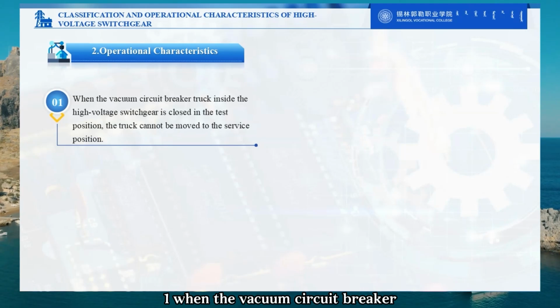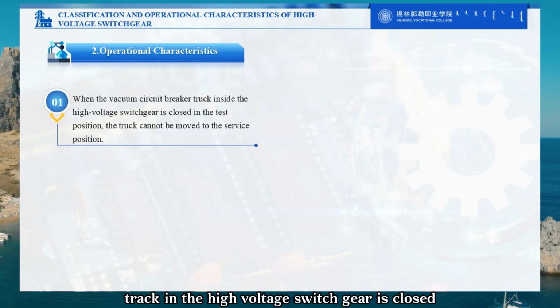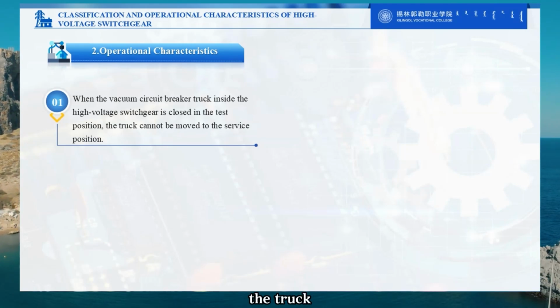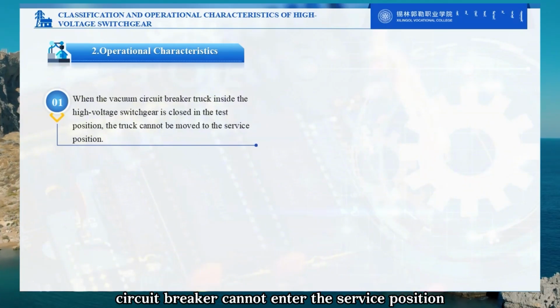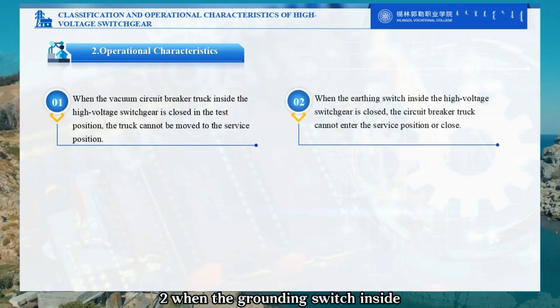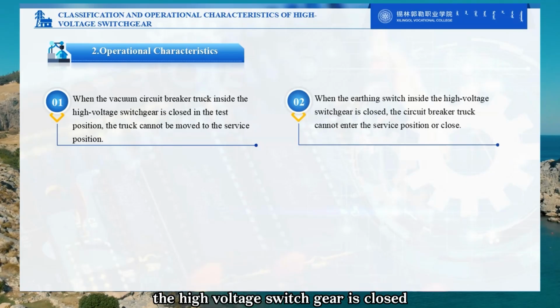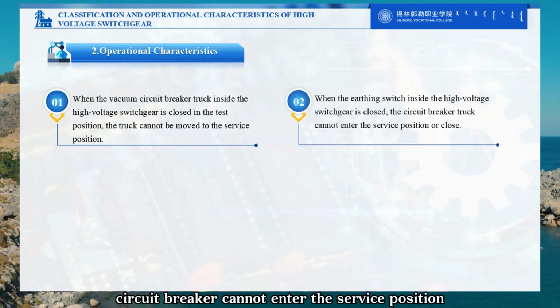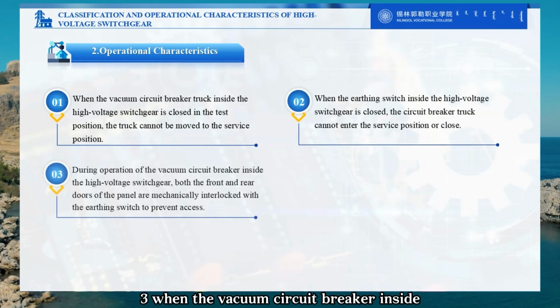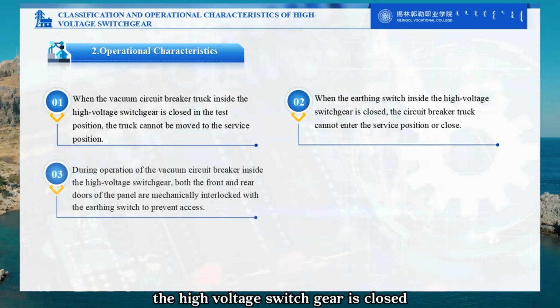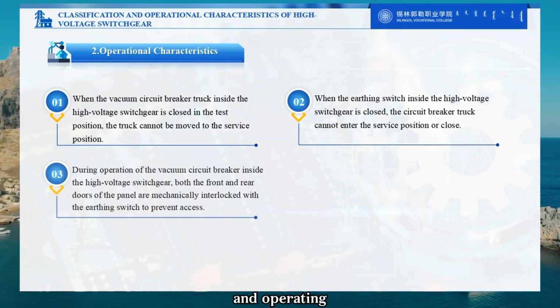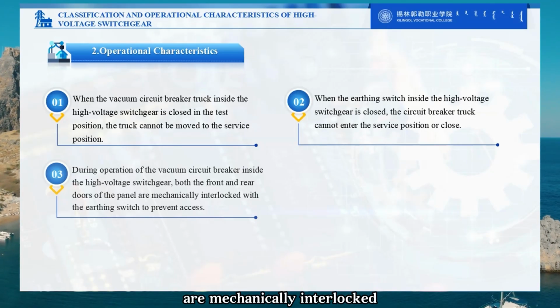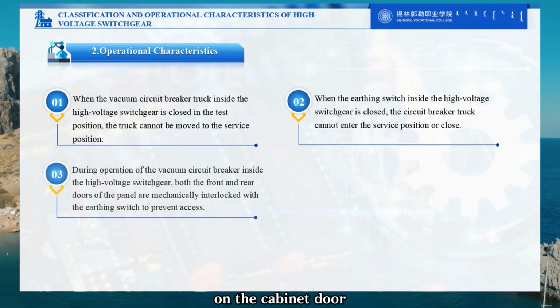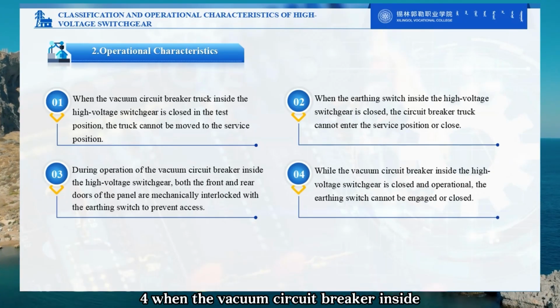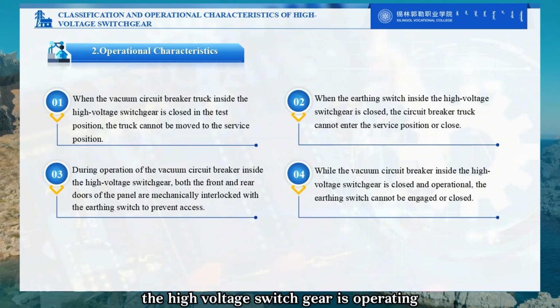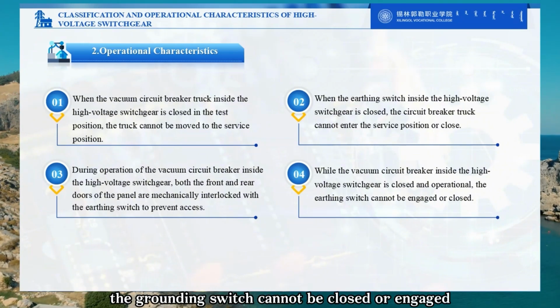1. When the vacuum circuit breaker truck in the high-voltage switchgear is closed in the test position, the truck circuit breaker cannot enter the service position. 2. When the grounding switch inside the high-voltage switchgear is closed, the truck circuit breaker cannot enter the service position or close. 3. When the vacuum circuit breaker inside the high-voltage switchgear is closed and operating, both the front and rear doors of the cabinet are mechanically interlocked with the grounding switch on the cabinet door.